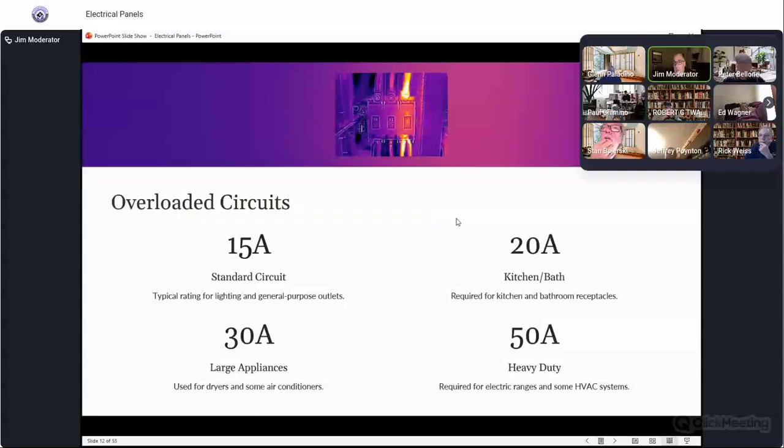A lot of times you'll see a homeowner run a sub panel out to a shed or a detached garage. I can tell you, if it was a homeowner special, I'll see it a lot of times. I saw one in Bristol a couple of months ago. It was 15 amp at best, and it was tied into a 100 amp breaker. It's like, what's going on there? The electrician no way did that.